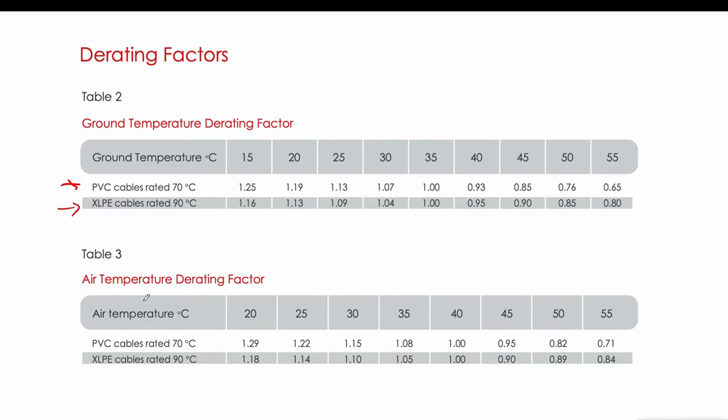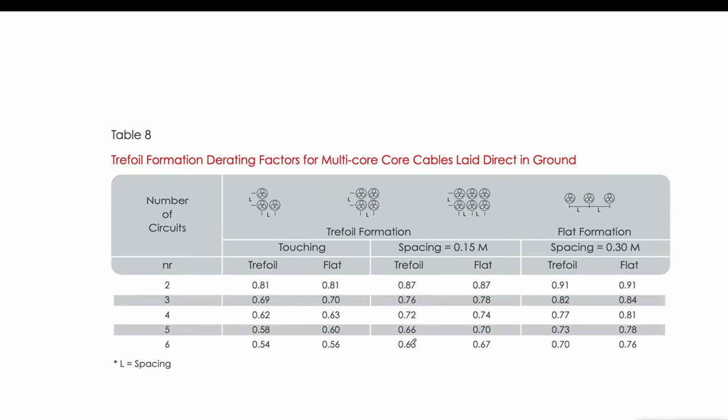Another derating factor is related to cables laid free in air. There is a derating factor related to this installation called the air temperature derating factor, and for this derating factor we have two types of insulation. According to insulation and ambient temperature of air, you will have different values of derating factors.